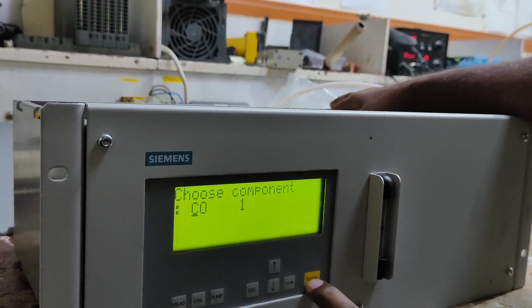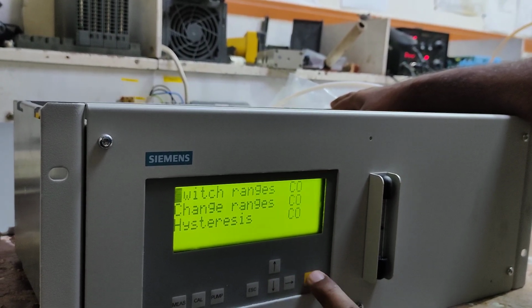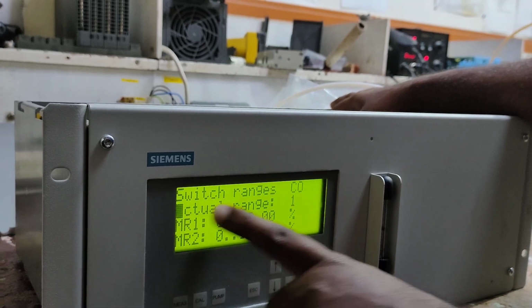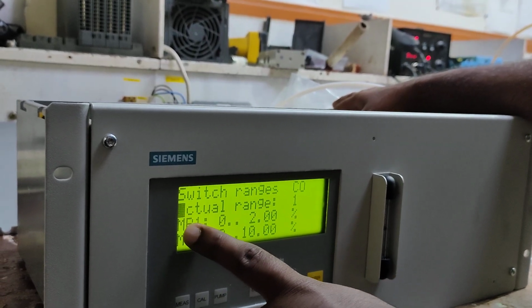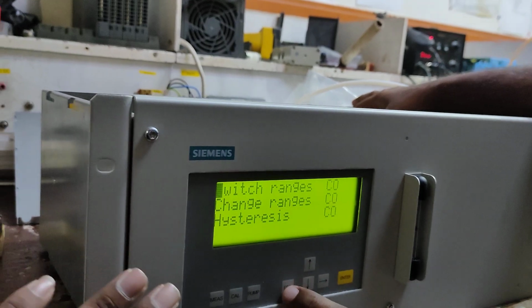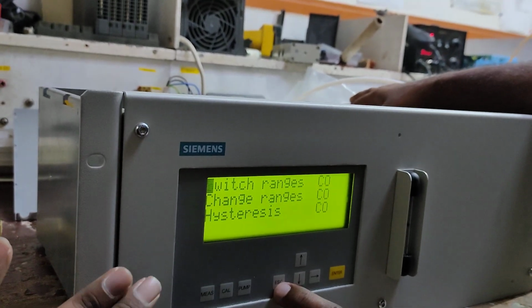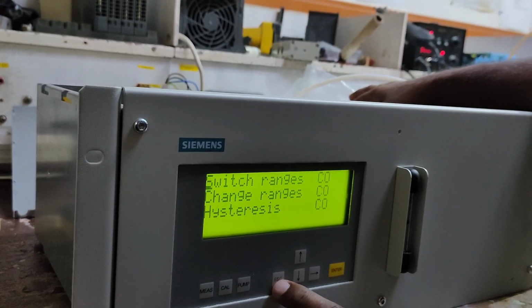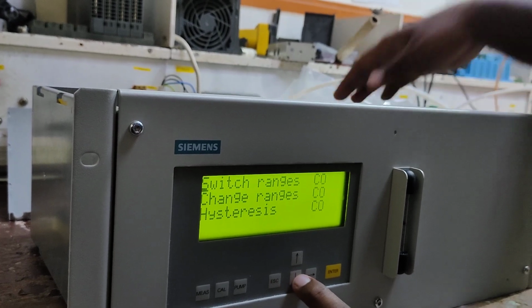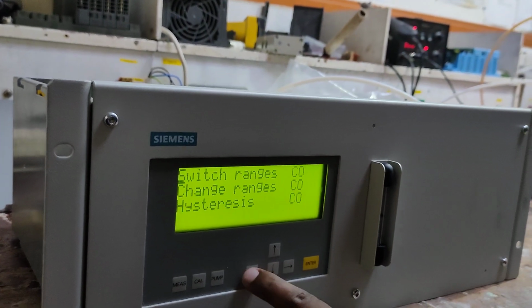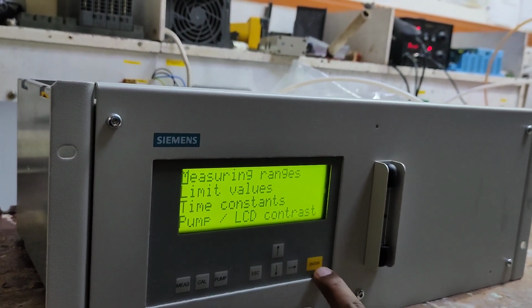So now we know the range of CO. CO should be range 1, 0 to 2%. Whatever you select, your 4 to 20 milliampere will be configured to that range. Only 4 to 20, 0 to 20 is not there. That also we can see and change. We can select here. Okay, measuring range.